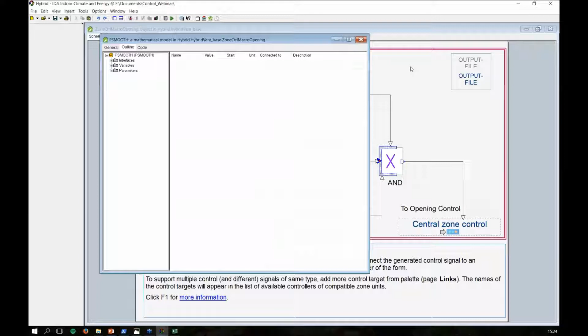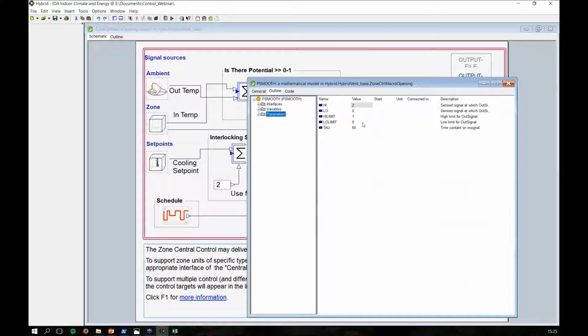So if I open this proportional controller and look at my parameters, basically I put my upper limit at 2 and my lower limit at 0. This means if the difference is anything between 2 and above, up to infinity, I'm going to send a signal of 1. This means, wow, a lot of potential there. If it's 0 and below, I'm going to send 0, so no potential.